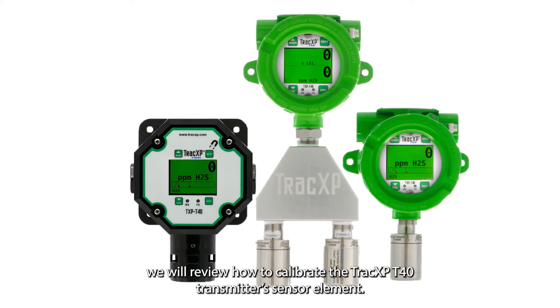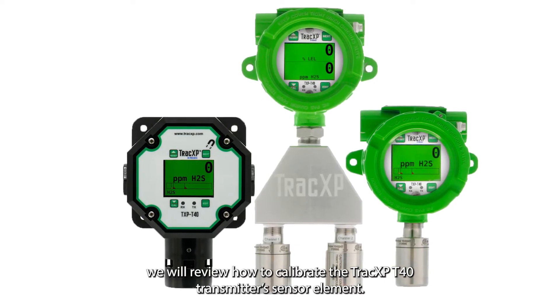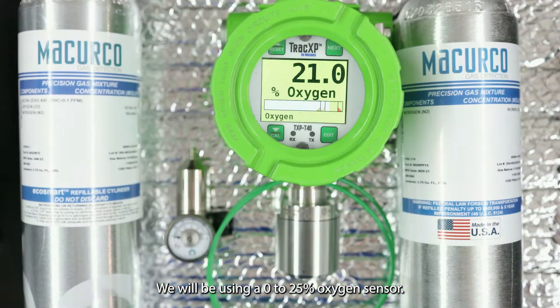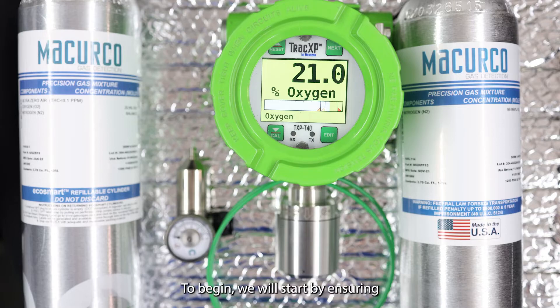In this video we will review how to calibrate the TracXP T40 transmitter sensor element. In this demonstration we will be using a 0 to 25% oxygen sensor, however this procedure applies to nearly every sensor type offered on the T40.